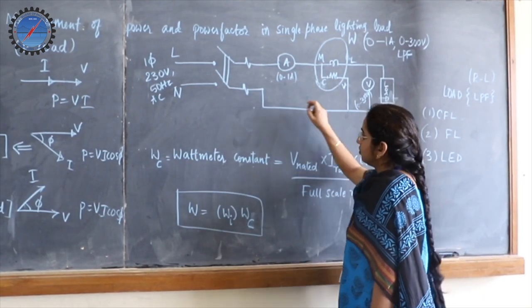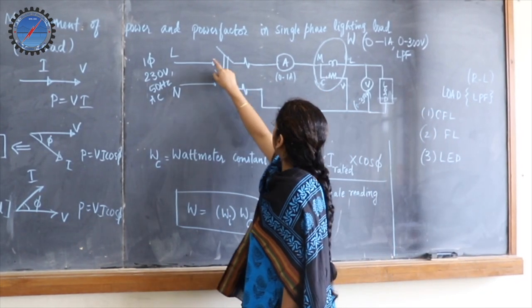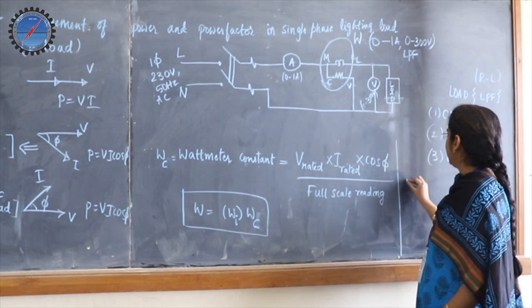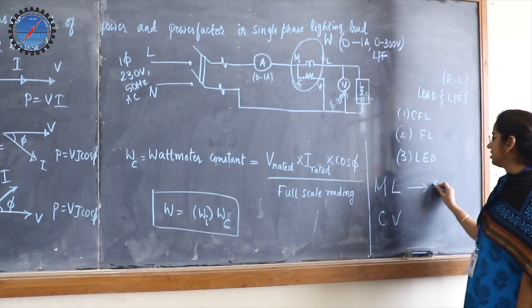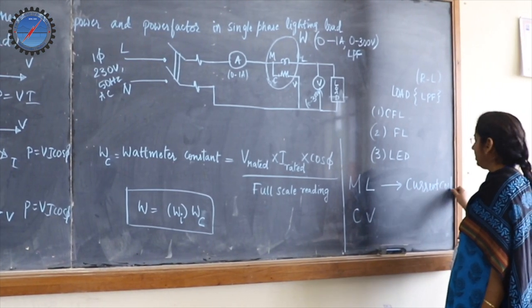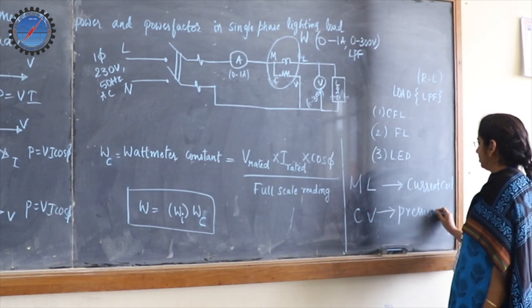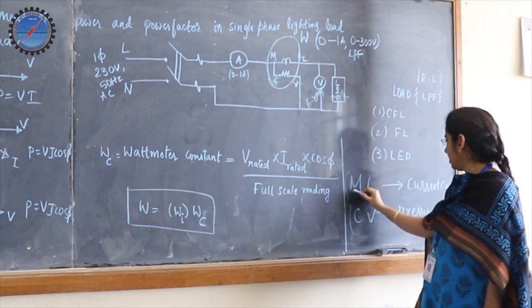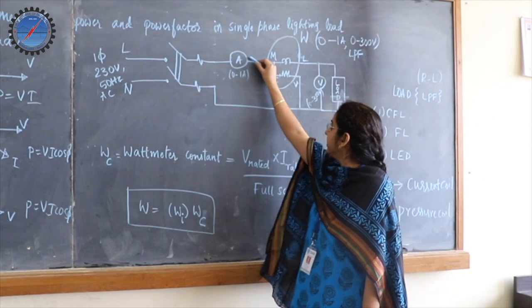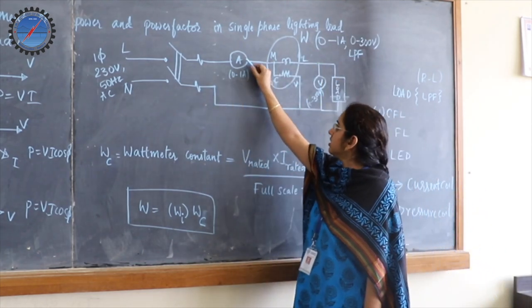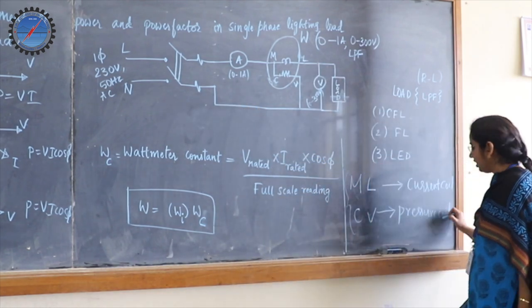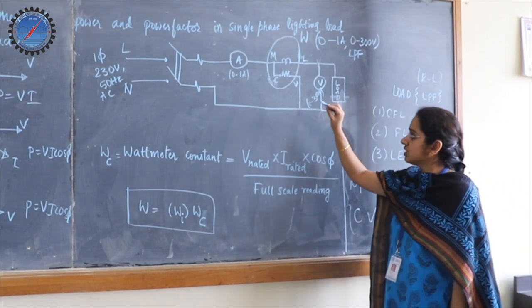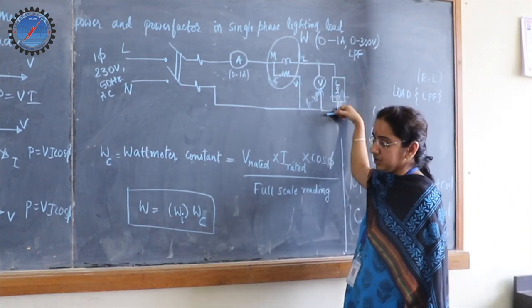To measure current through the network, we always connect an ammeter in series. The supply goes to the ammeter to record the current, then it goes to a wattmeter. A wattmeter has four terminals: M, L, C, and V. M and L correspond to the current coil terminals, and C and V correspond to the voltage coil or pressure coil terminals. M and L are connected in series with the network, and C and V are connected across the load terminals where voltage is to be sensed.